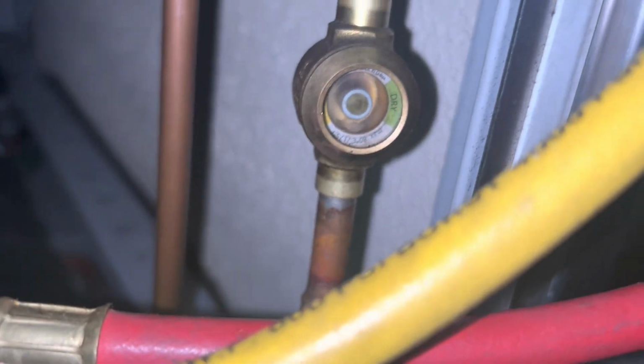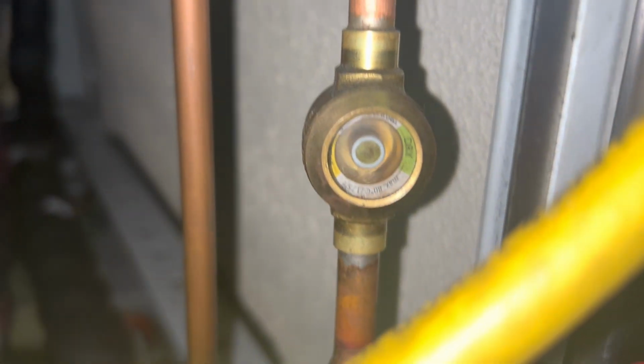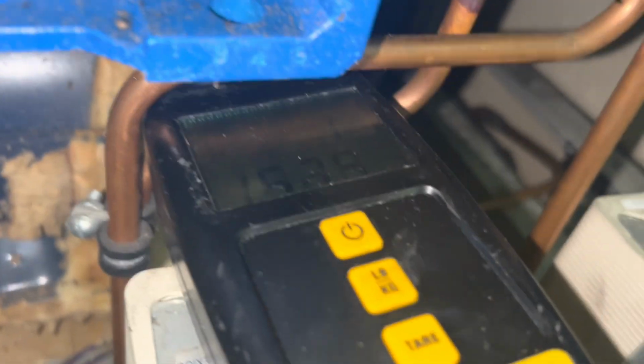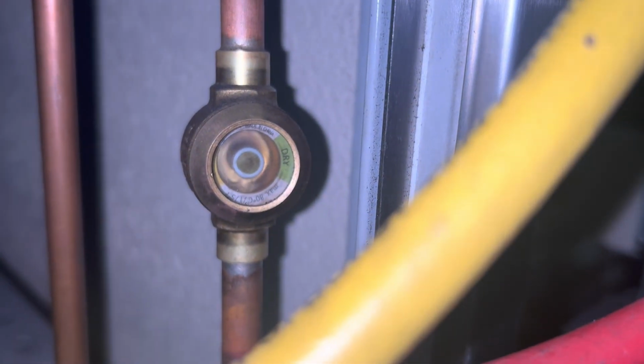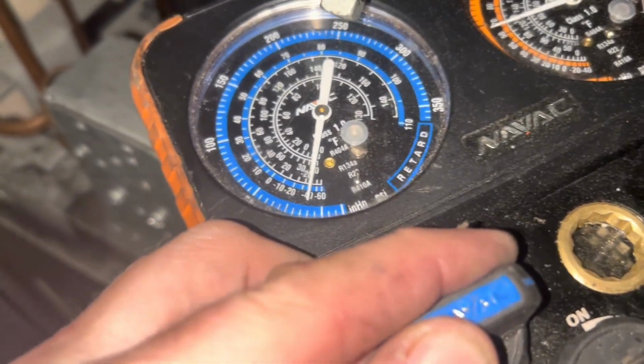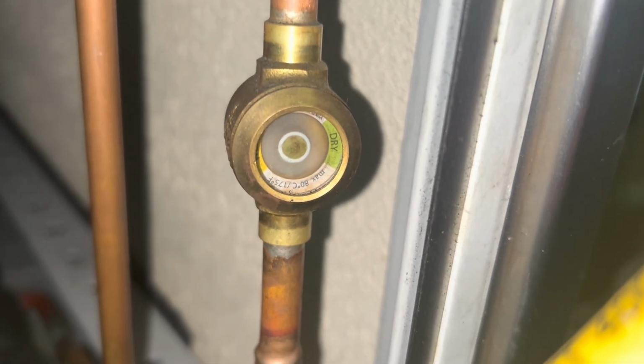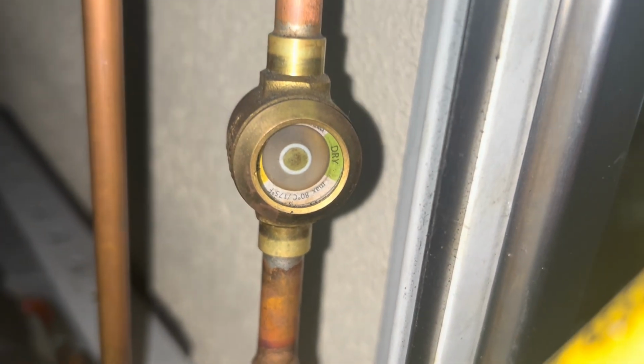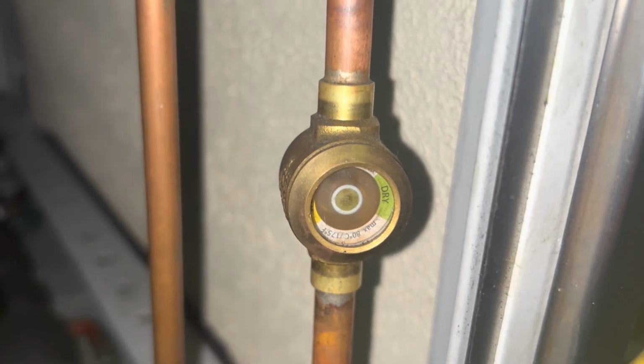Well, what if it can run on 7 pounds just fine? And beyond 7, the receiver starts struggling. We're at 2 pounds now. The receiver starts struggling and gets so low it can't function. So you can be 3 pounds short and the system becomes inoperable, because that's less than the receiver.